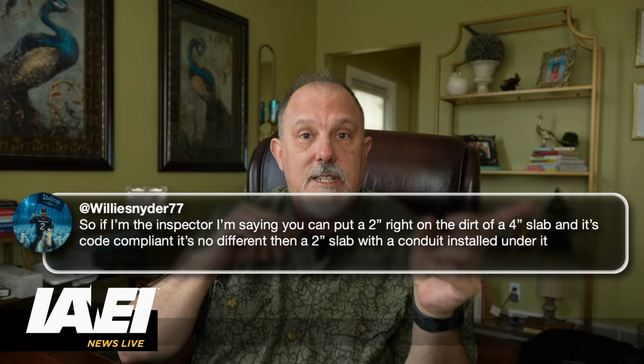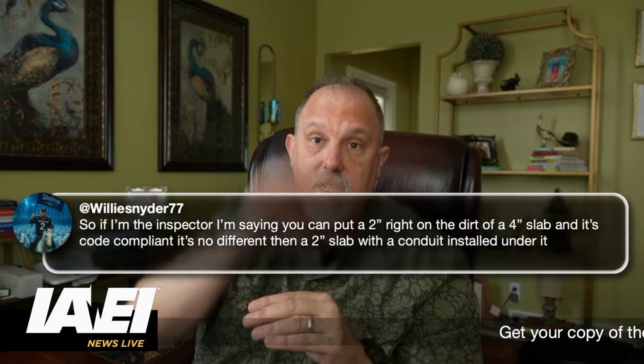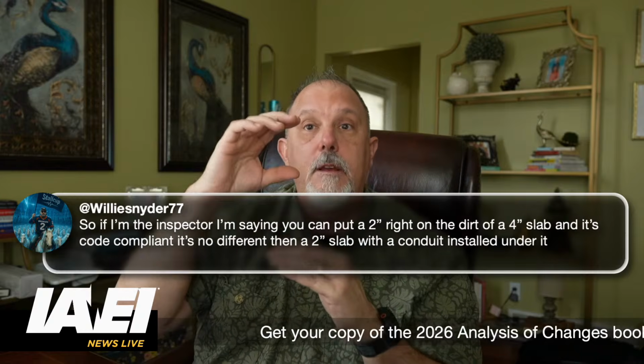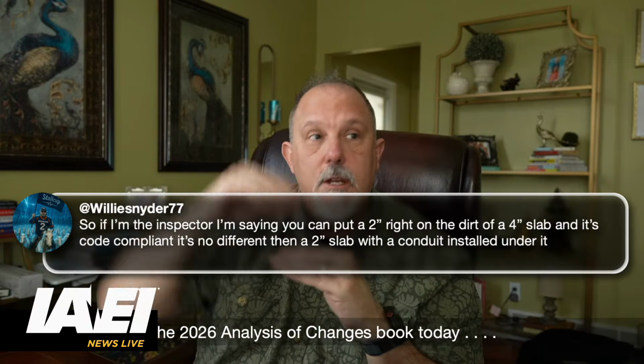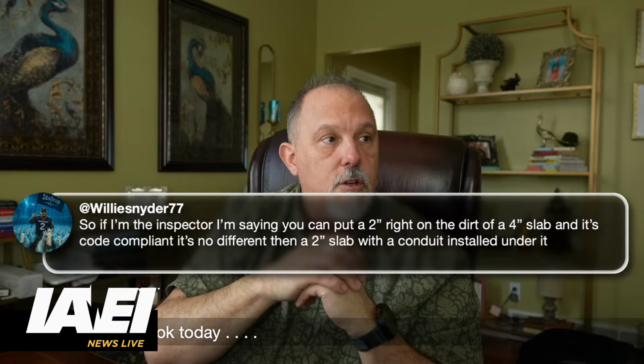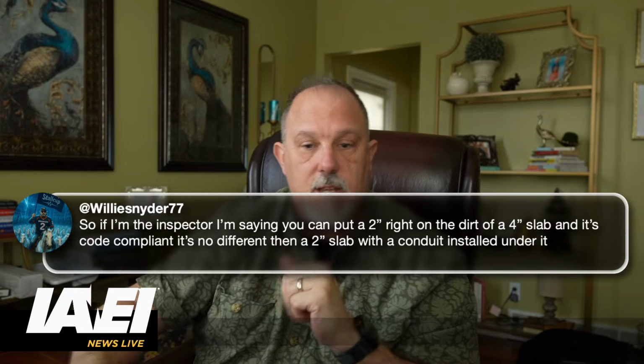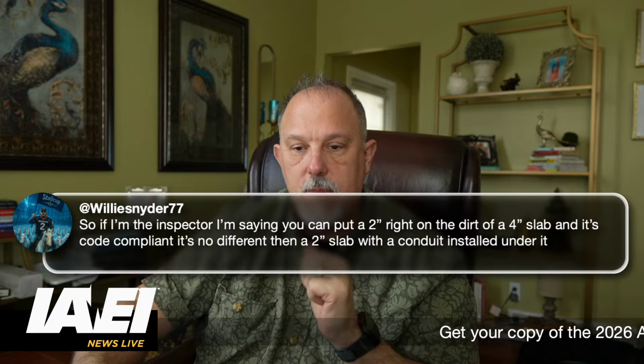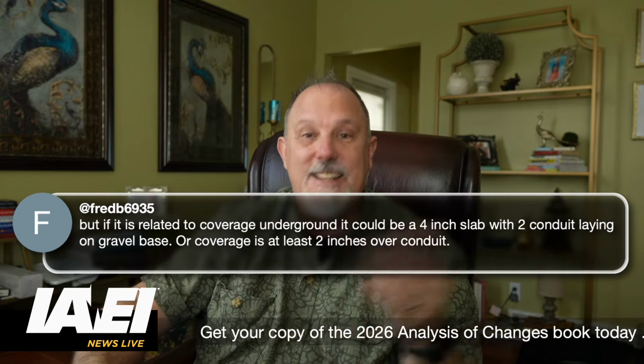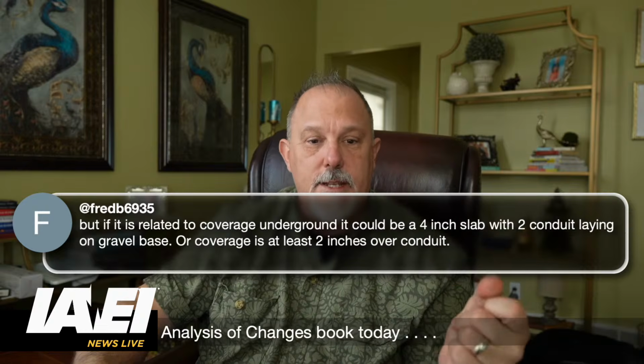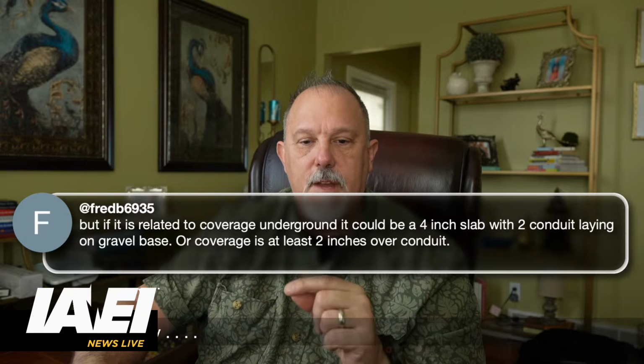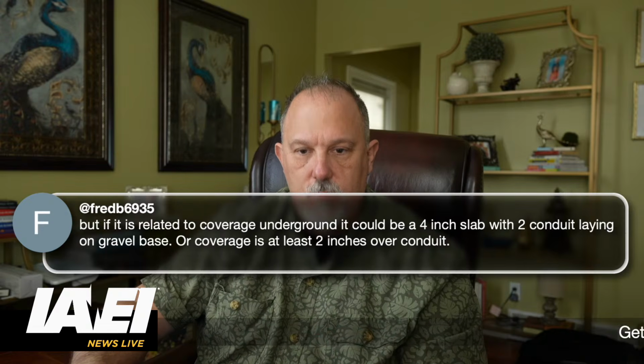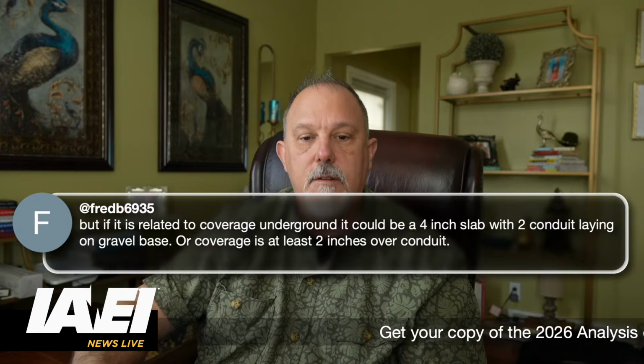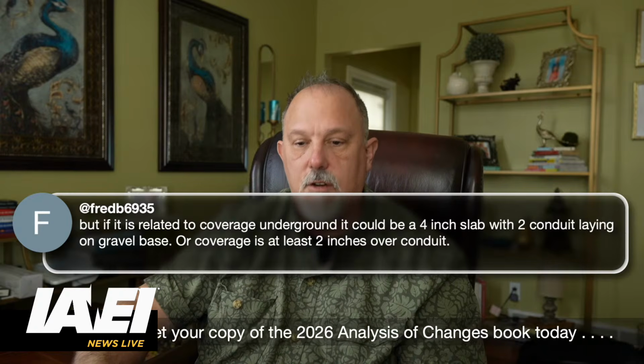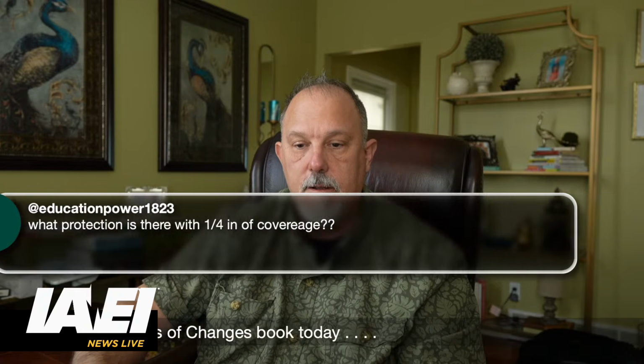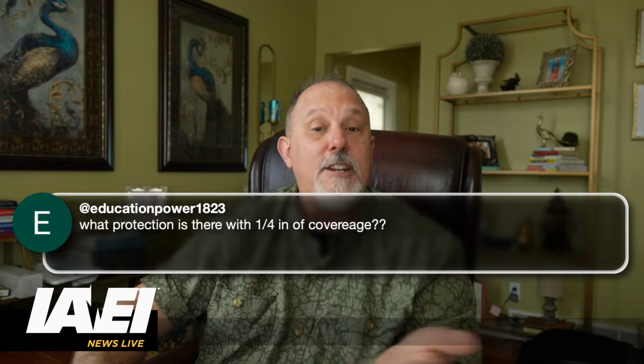I think that it doesn't really say that. And we say that in exception number 2. We tell you that the concrete has to be on top of it, and we give you the measurement from the top of the raceway to the top of the concrete, but we don't do the same thing for exception number 3. I love this. But as soon as you start making public inputs, people are like, whoa. But if it's related to coverage underground, it could be a 4-inch slab with conduit laying on a gravel base, or coverage is at least 2 inches over the conduit. Yep, I would agree with that. What protection is there with a 1/4 inch of coverage? I know, Robert, that's my point.